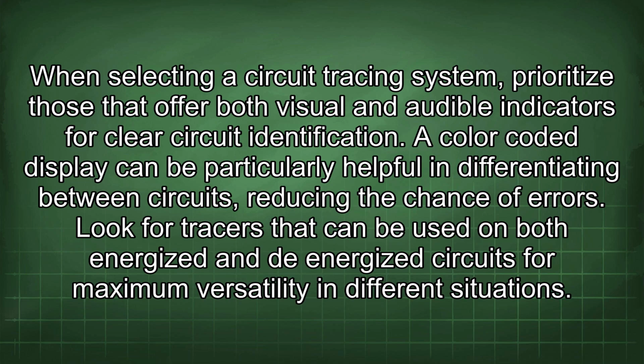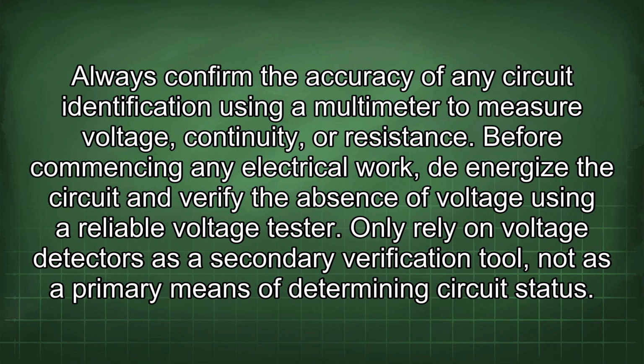Look for tracers that can be used on both energized and de-energized circuits for maximum versatility in different situations. Always confirm the accuracy of any circuit identification using a multimeter to measure voltage continuity or resistance. Before commencing any electrical work, de-energize the circuit and verify the absence of voltage using a reliable voltage tester. Only rely on voltage detectors as a secondary verification tool, not as a primary means of determining circuit status.